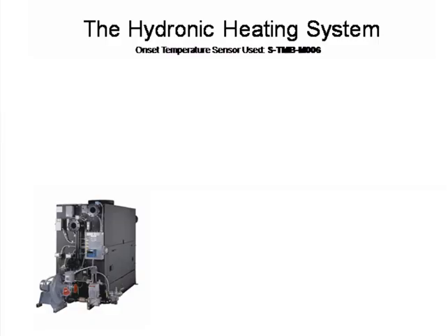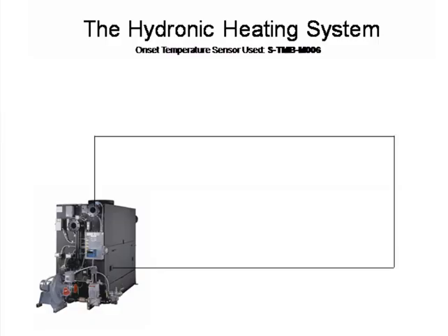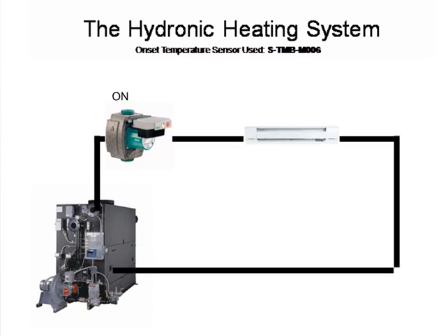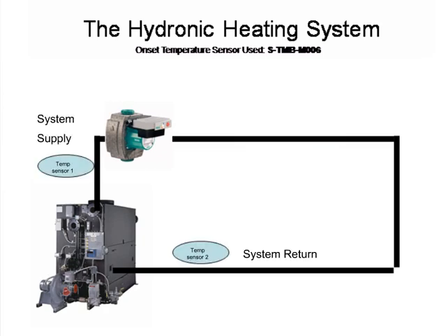Let's look at the critical sensor placements. The first is the system supply — this sensor shows us the actual supply temperature being delivered to the building by the heating system. The second sensor is placed on the system return pipe. The differential in temperature between these two points is a major indication of the real-time demand being placed upon the heating system, but we're not done yet by any means.